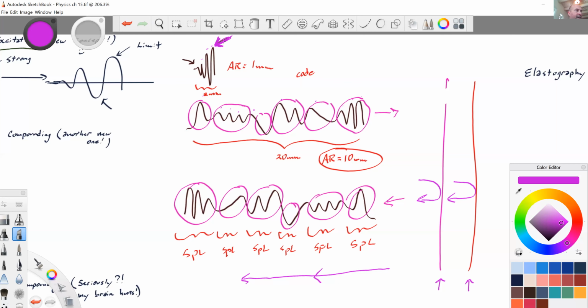Coded excitation creates very long sound pulses containing a wide range of frequencies. This design pulse distributes energy over a broad frequency range. The coded pulse is strong, but keeps the peak intensity below the FDA limit. So as you can imagine, the overall energy put into the body is greater with coded excitation. I mean, just look at the spatial pulse length. It has to be greater, right? But that peak intensity, that's the dangerous part.